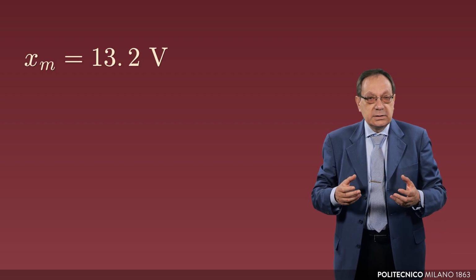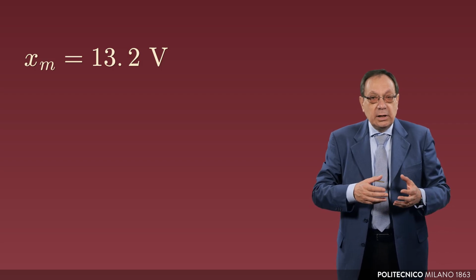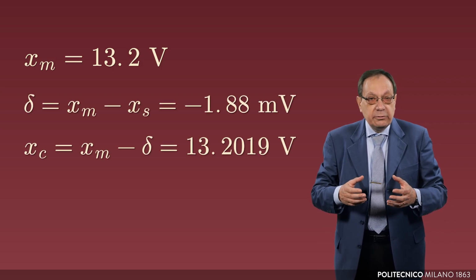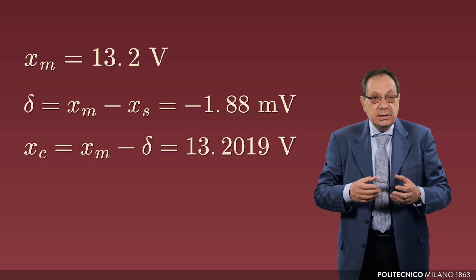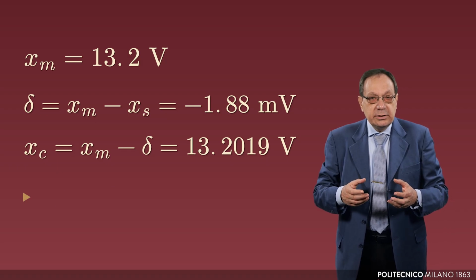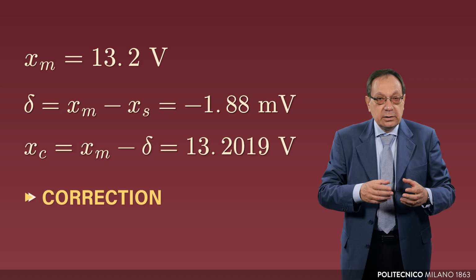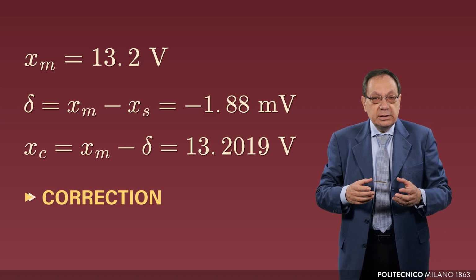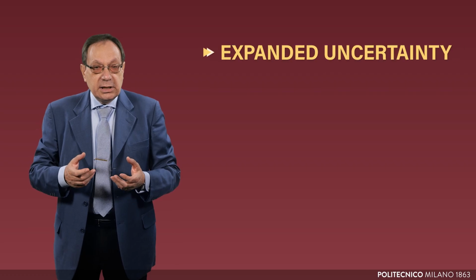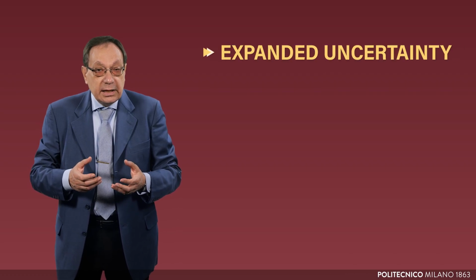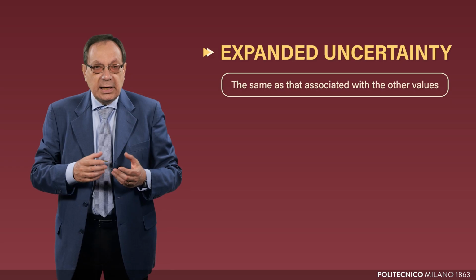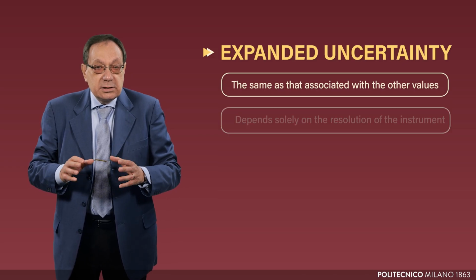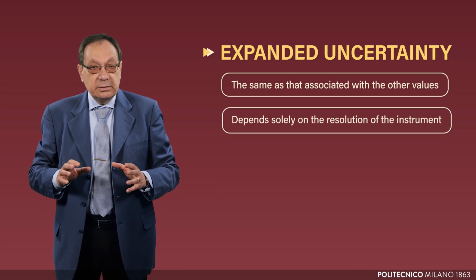For example, if the calibrated instrument gives a reading of 13.2 volts, from the equation of the line, one obtains a deviation delta equal to minus 1.88 millivolts. This is the correction to be applied, and therefore the value to be attributed to the measure is the one you see on the slide. The expanded uncertainty to be associated with the corrected value in this case is the same as that associated with the other values, since it depends solely on the resolution of the instrument.